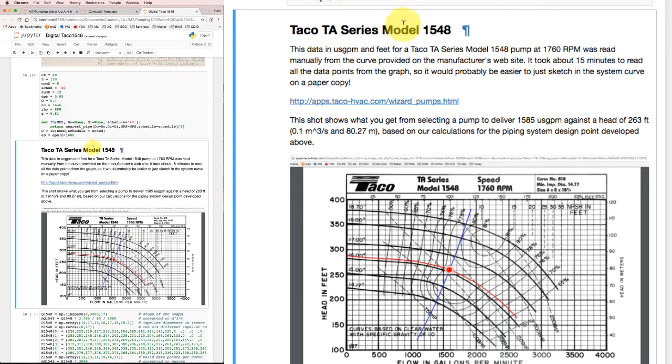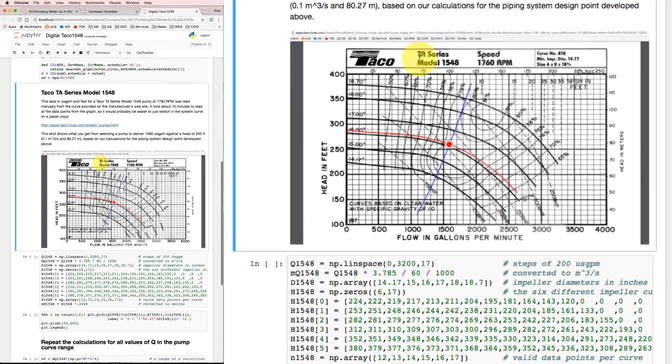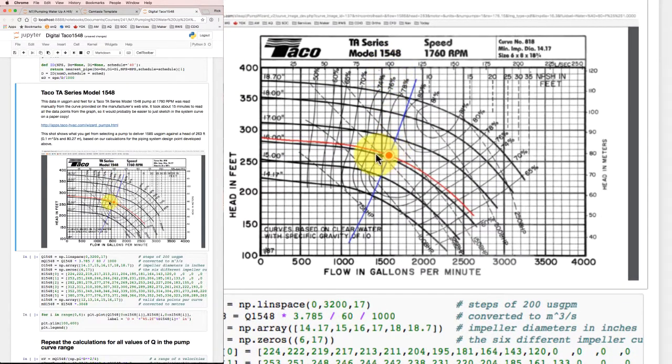Having set all of those values, we need to have a pump to work with and a way that we can make some models happen. So previously we've decided that a TACO TA series model 1548 might be a good choice and we went to the TACO pump selection site and we were able to find this graph for our input values of 0.1 cubic meters per second at a head of 80.27 meters.